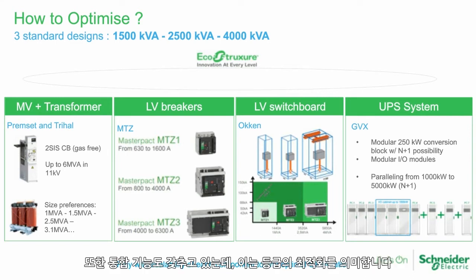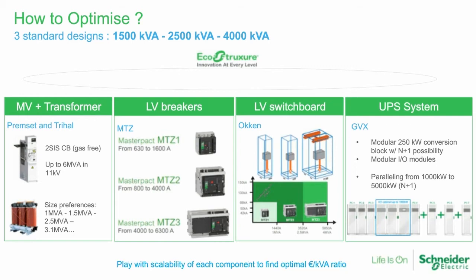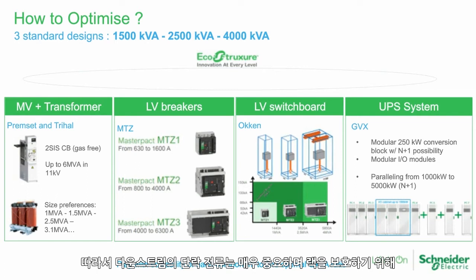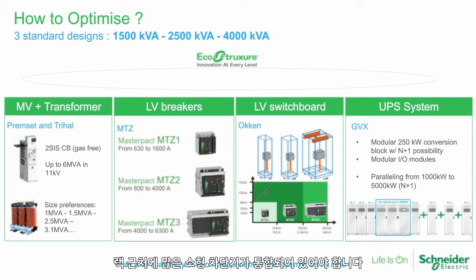We also have integration, meaning optimization of the ratings. The short circuit current on the downstream is very critical, and there are a lot of small breakers that need to be integrated close to the rack to protect the racks. And we have to consider this short circuit current end to end.